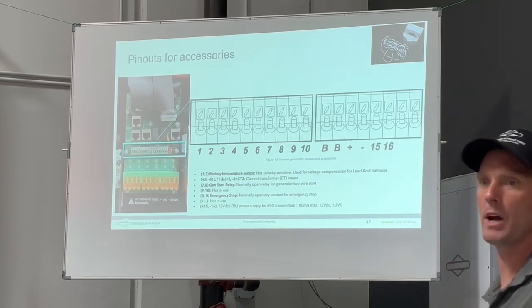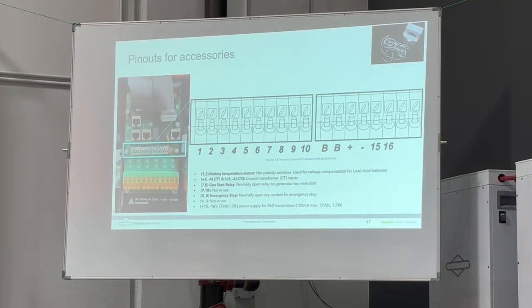You don't have to do that with lithium batteries, and you definitely don't have to do that with communicating batteries. The voltage state of charge curve with temperature for lithium batteries doesn't really change much. There's not a whole lot of variation between the voltage for a lithium battery as the temperature changes. But pins 3 and 4, those are where your CTs will go, CT number 1, and then 5 and 6 for CT number 2. That would be your leg 1 and your leg 2 coming from utility.